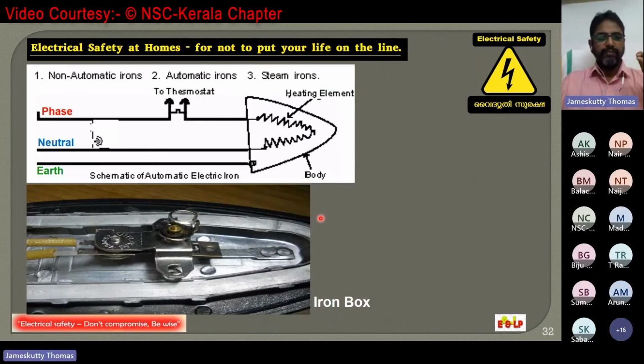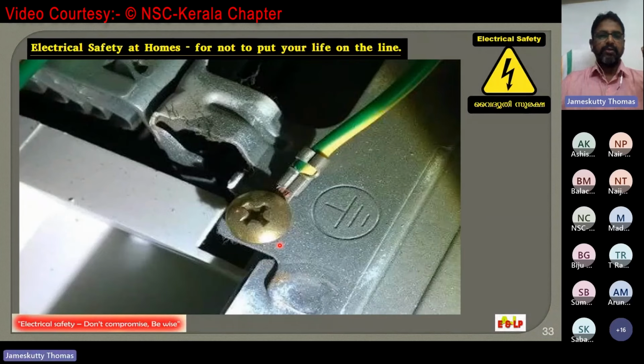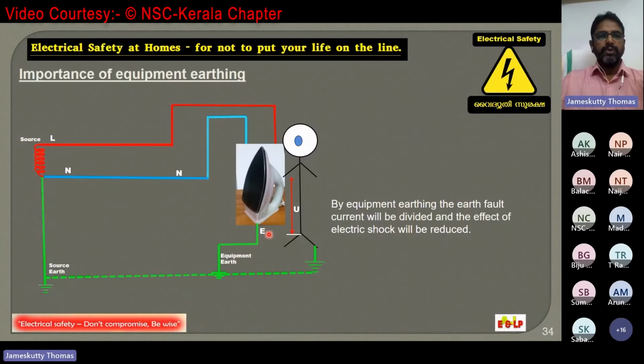Now let us see how we can use an earthed iron box and how we are getting protection. Here you can see phase, neutral and earth. Here phase and neutral will be inside the filament. And now see here, through our 3-pin plug, the body of this iron box will be earthed through the 3rd earth pin. While we are using the iron box, there can be chances of leakage to its body. The body of the iron box can be live while we are using it, but since it is earthed through the 3rd pin, when we connect it, the leakage protection such as an ELCB or RCCB can trip.